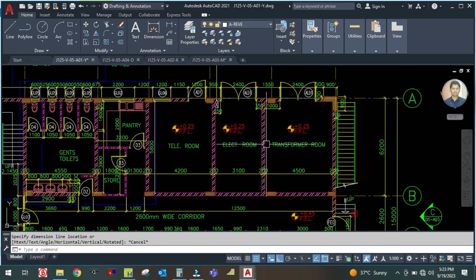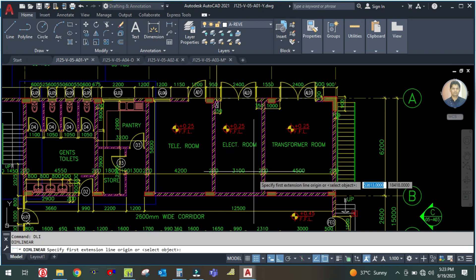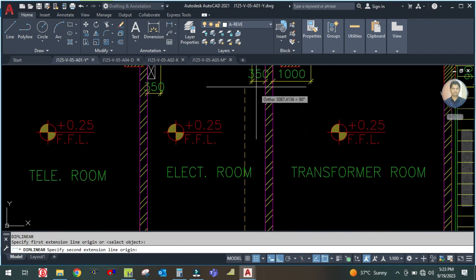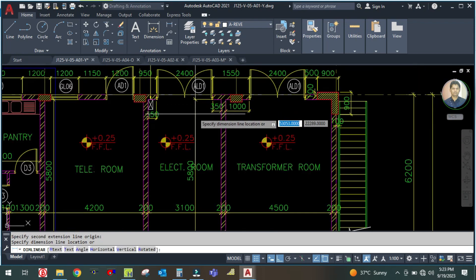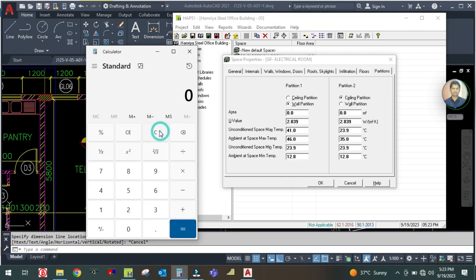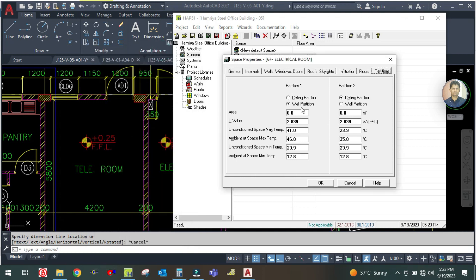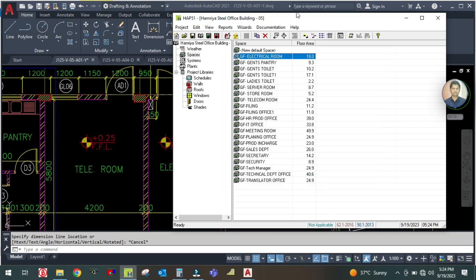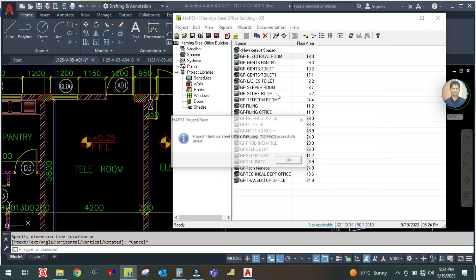There is a partition here because the transformer room is an unconditioned space, so select the partition. The length of this room is 5.8 by 4 meters, which is 5.8 × 4 = 23.2 square meters. Enter 23.2 square meters for the wall partition. The U-value stays the same — do not change anything. Click OK and save.